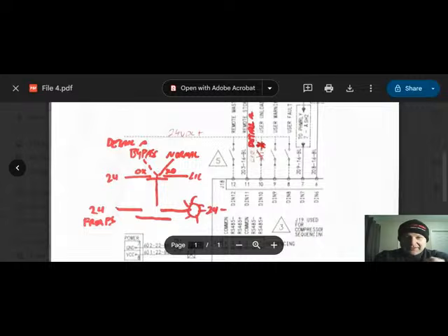So it doesn't necessarily have to be a lighting circuit either. I mean, this user unload could be anything. It could be something from the customer's control system that they go, well, we don't want the compressor to run when we're doing X. So okay, when that process kicks off, give me a dry relay here, and we'll make that happen.